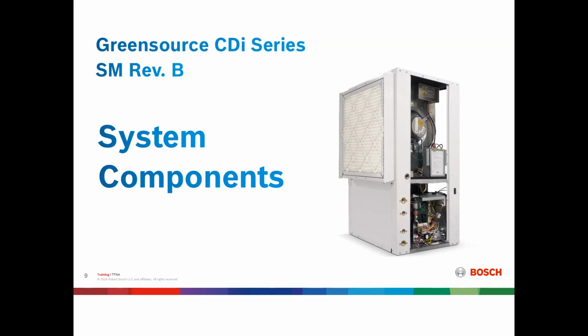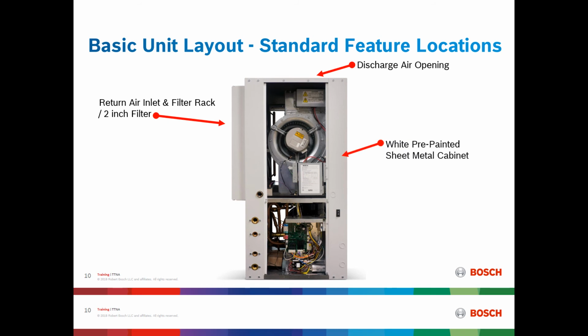Now let's look at some of the standard system components that come with the SM Rev B model. Here we see the basic unit layout with standard feature locations. We see that this one shows the return air inlet and a filter rack which could hold up to a 2-inch MERV 8 filter. On the top of the unit is where the discharge air opening would be. In a counterflow application, it would be reversed and on the bottom. This unit is made with white pre-painted sheet metal. Additionally, it has a constant CFM variable speed blower.